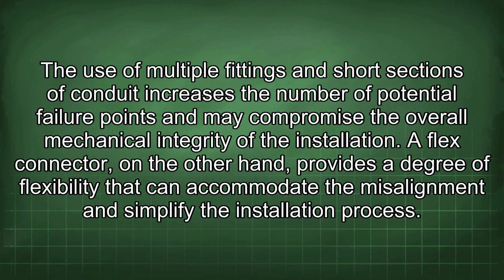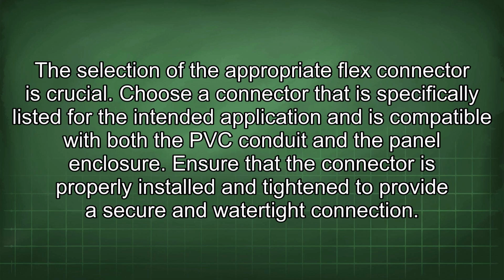A flex connector, on the other hand, provides a degree of flexibility that can accommodate the misalignment and simplify the installation process. The selection of the appropriate flex connector is crucial. Choose a connector that is specifically listed for the intended application and is compatible with both the PVC conduit and the panel enclosure. Ensure that the connector is properly installed and tightened to provide a secure and watertight connection.